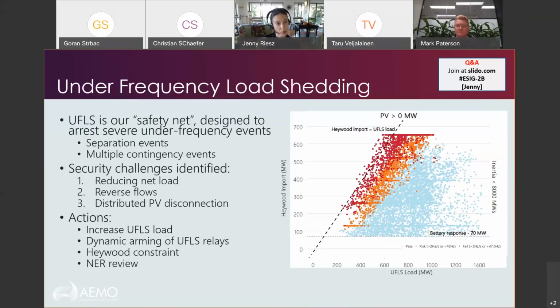So there's a whole suite of actions underway to manage this issue as well. We're increasing the amount of load in the under-frequency load shedding, putting as much load in there as we can to try and boost the capability. We're introducing dynamic arming of UFLS relays, so it will be much smarter and more responsive. We're putting in place a new constraint, which will be happening very, very soon. That's in the final stages of working through our process at the moment to limit flows on the Heywood interconnector when we know that the under-frequency load shedding is not adequate and increase the probability of forming a stable island. And we're also looking at these frameworks under the national electricity rules and how they need to change longer term to put in place the enduring frameworks we're going to need. Next slide.